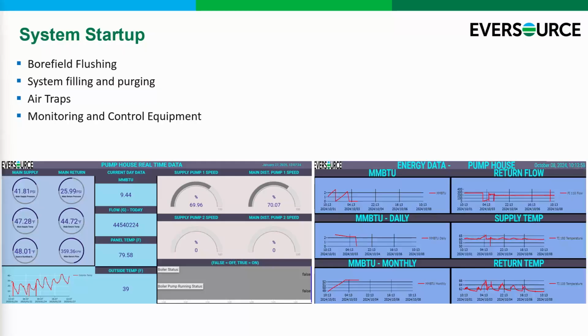So getting that system up and running was almost step one. Before I could even add a single customer, I wanted to be able to see the system remotely in a web-based SCADA. In addition to that, bore field flushing, pressure testing, getting air out of the system, these are all steps that we had to take as we turned it on, as we started the pumps up, and as we added customer loads to make sure that there wasn't any disruption in service.